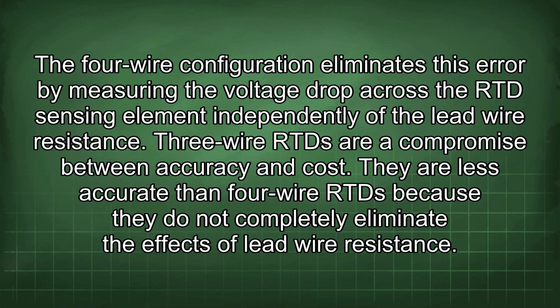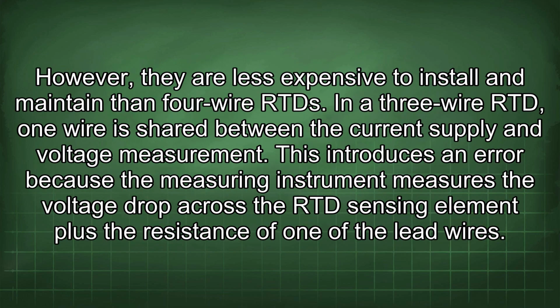They are less accurate than 4-wire RTD because they do not completely eliminate the effects of lead wire resistance. However, they are less expensive to install and maintain than 4-wire RTD. In a 3-wire RTD, 1 wire is shared between the current supply and voltage measurement. This introduces an error because the measuring instrument measures the voltage drop across the RTD sensing element plus the resistance of one of the lead wires.